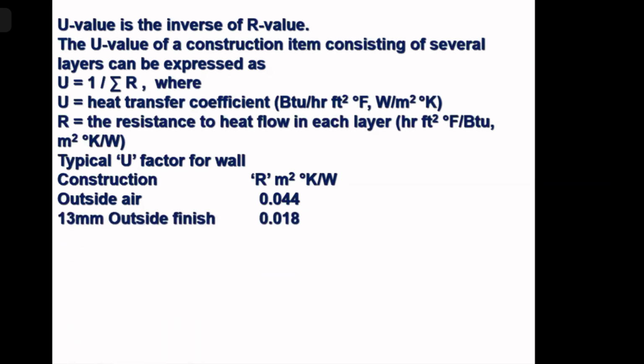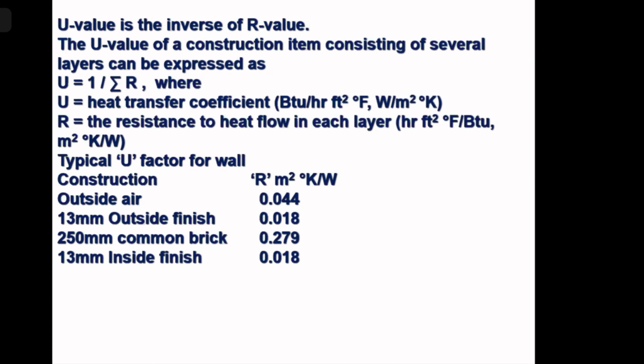Then after that outside air film, we have outside plaster, half-inch plaster, 13mm plaster. For that, R value is 0.018. Next we have common brick. 250mm common brick wall, for which we have 0.279 R value. Next. Then we have inside plaster, half-inch, again 0.018. Then we have inside air film, for which R is 0.12.